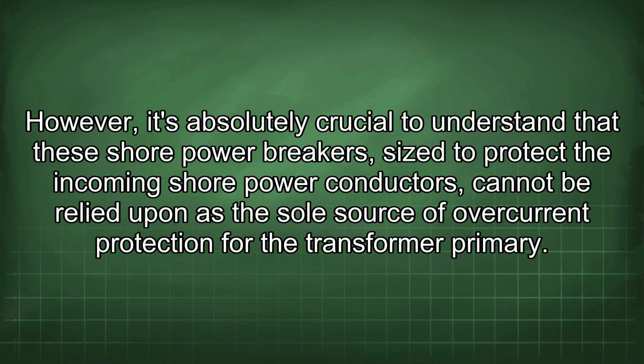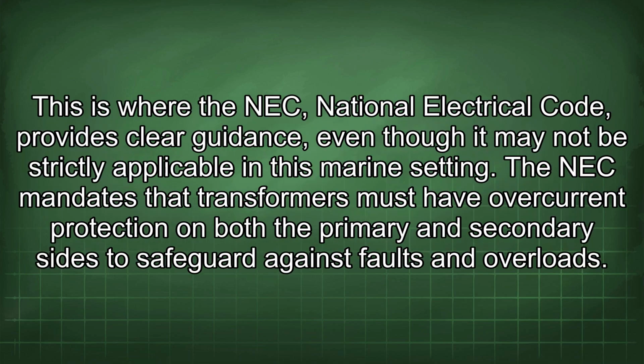However, it's absolutely crucial to understand that these shore power breakers, sized to protect the incoming shore power conductors, cannot be relied upon as the sole source of overcurrent protection for the transformer primary. This is where the NEC, National Electrical Code, provides clear guidance, even though it may not be strictly applicable in this marine setting. The NEC mandates that transformers must have overcurrent protection on both the primary and secondary sides to safeguard against faults and overloads.